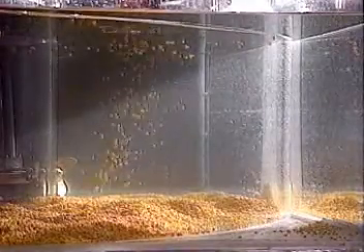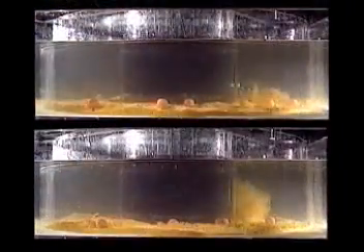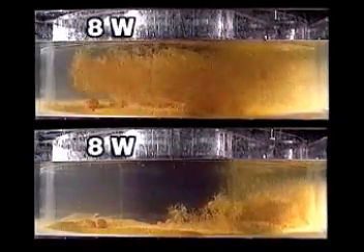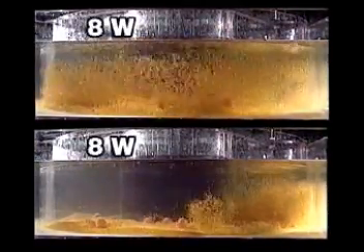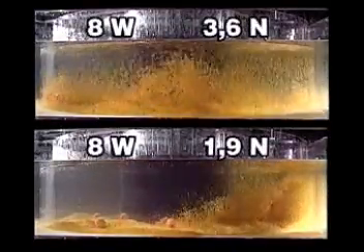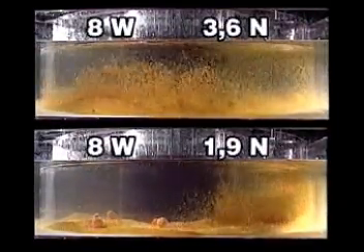Ping-pong balls may seem quite far removed from real applications, so we replace them with solid plastic particles having a density higher than that of the water. Again, it's important to note that power input to the mixer is equal in both of these examples, eight watts. Note the difference in bulk flow velocity and degree of suspensioning.